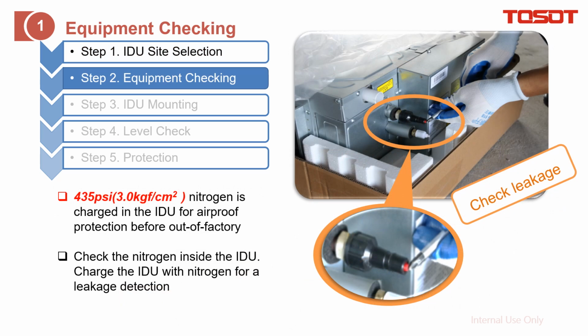The next step is to check the airtightness of the indoor unit. For each indoor unit, either duct type or cassette, before it leaves the factory we charge 3 kgf of nitrogen inside. So on site you just need to press this pin like this. If you can feel air coming out, that means the airtightness is okay. Otherwise you need to check where the leakage is.